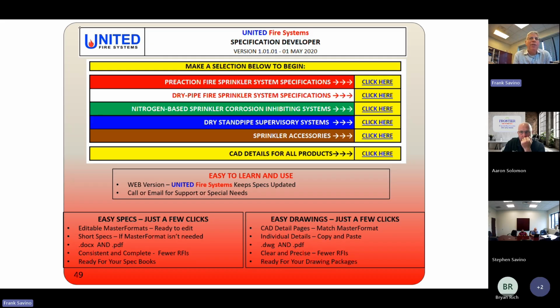And that applies to also detection technology. You have to be knowledgeable in all the various detection technology that are coming down the pike. You've got spot high sensitivity detection, VESDA, you've got now thermographic imaging that's coming on the scene. So knowing all these different tools helps you select the best detection, the best suppression, and then you put it all together in a unified system along with the interfacing with HVAC controls and things like that. It's a total systems approach. But again, knowing that this exists and what you can do with it is the first step in solving problems for your customers.